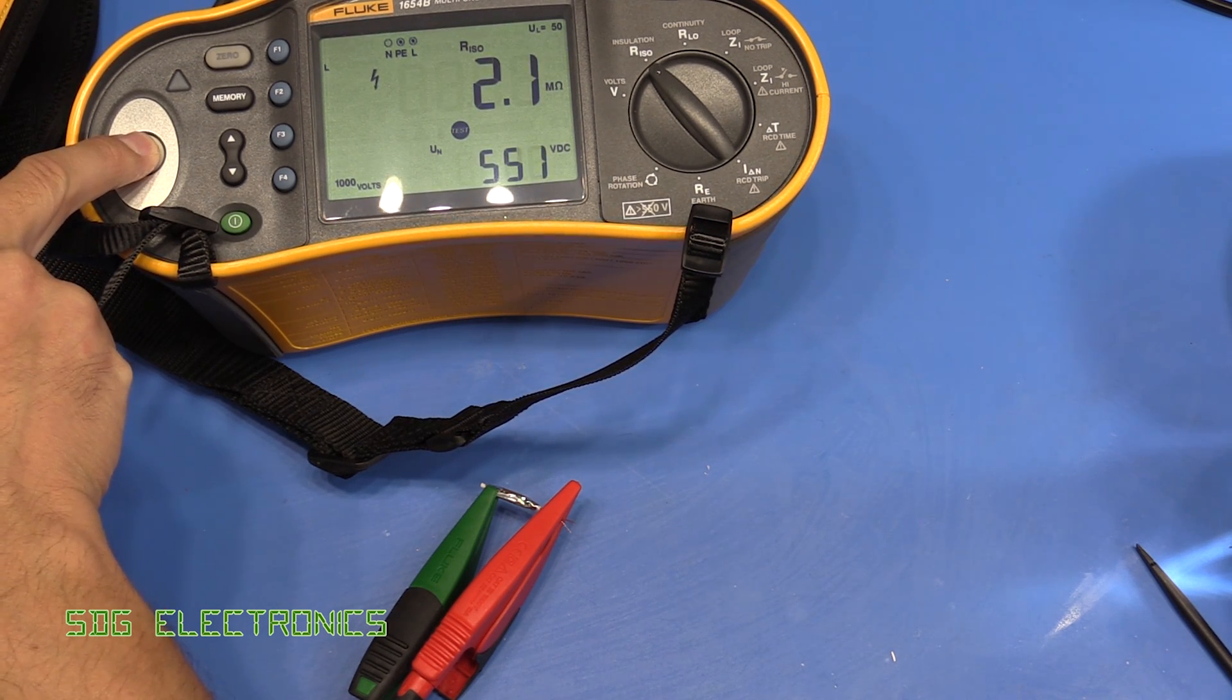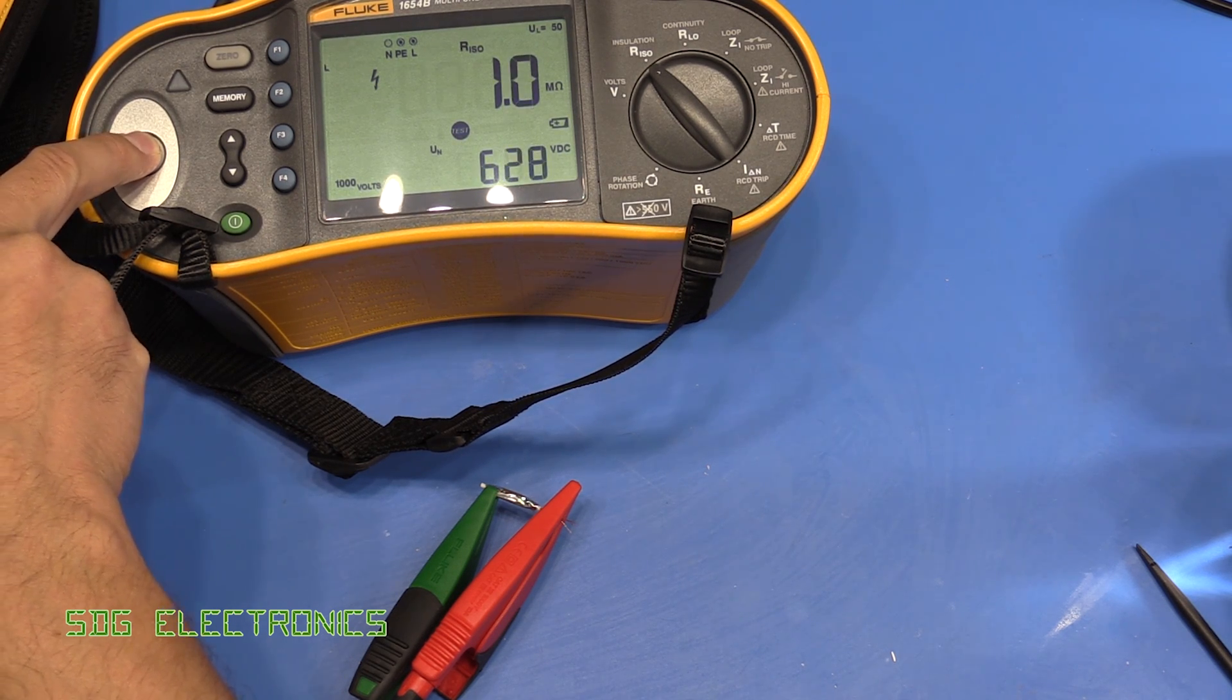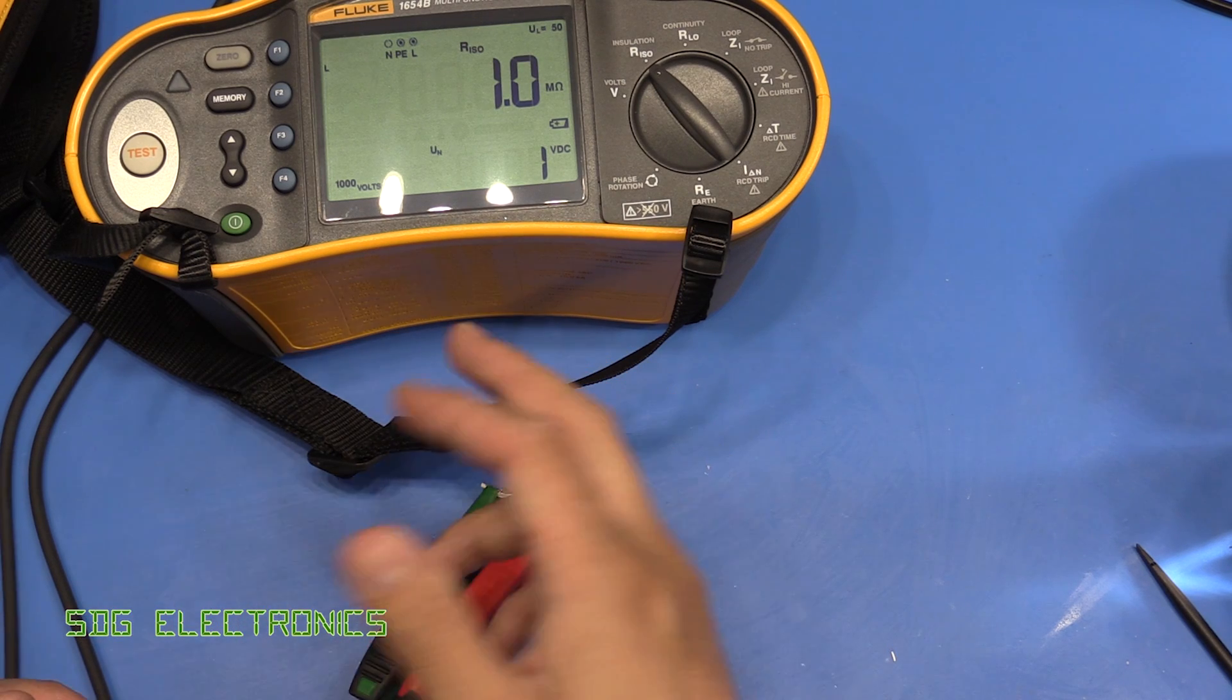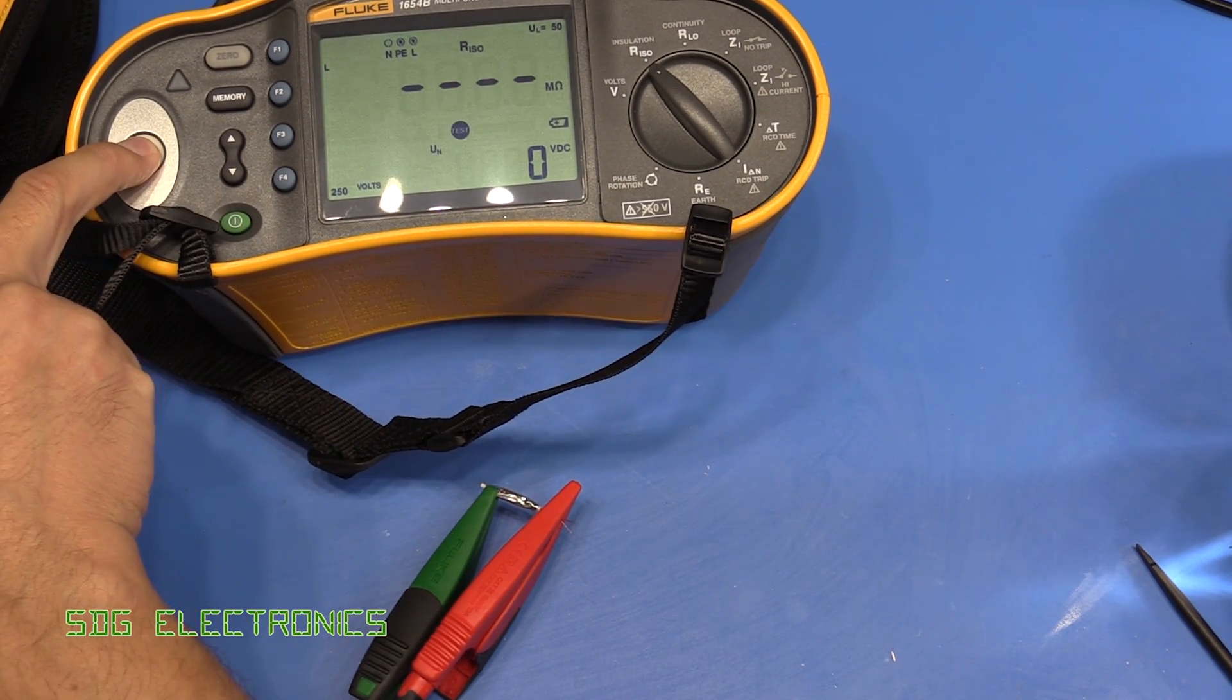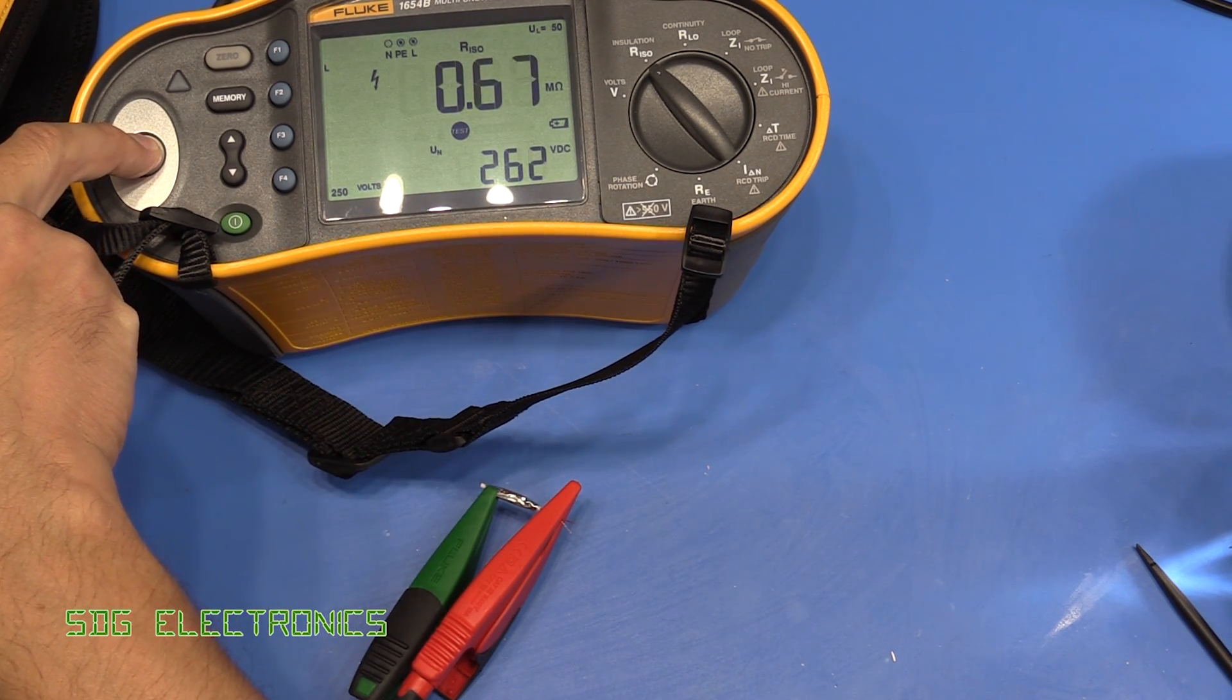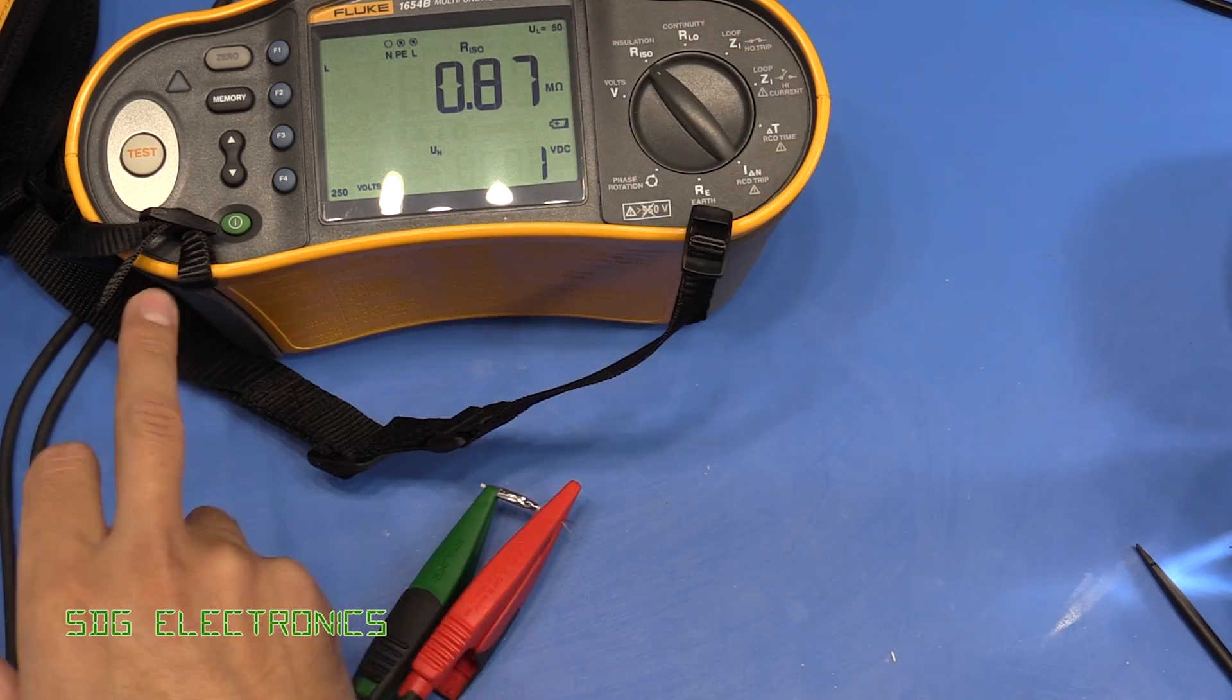You can hear it crackling away. It's reading about 2 mega ohms and going down, so we have broken down the insulation there. This suggests it's not suitable for a thousand volts. It was probably okay at 250 volts, but we are getting some lower readings.